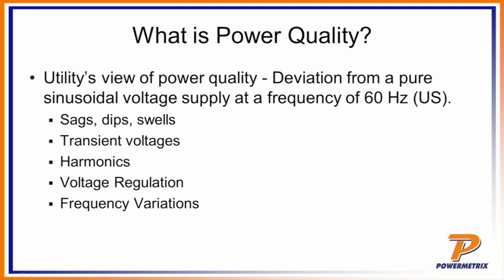But to just go into the subsets of things that we see in power quality, we're going to talk about sags, dips, and swells, which is just really a variation in the voltage of your system. Transient voltages, which are very short momentary problems in your voltage system. Harmonics, we'll talk about that quite a bit because a lot of modern loads have harmonics, so we'll talk about what is a harmonic and how does that affect you. Voltage regulation, and then finally frequency variations.